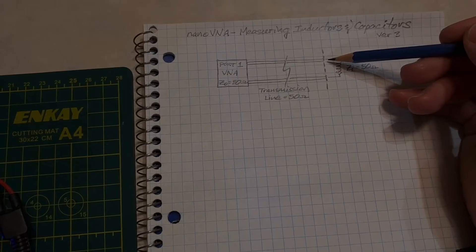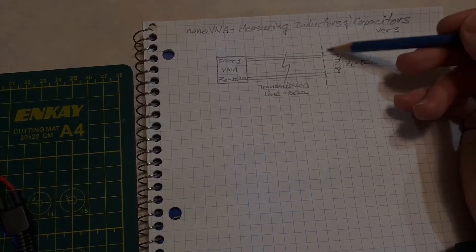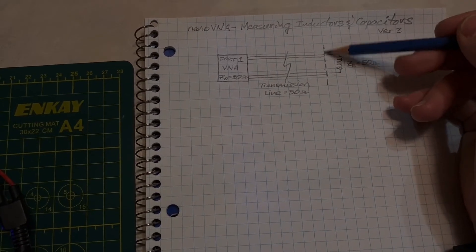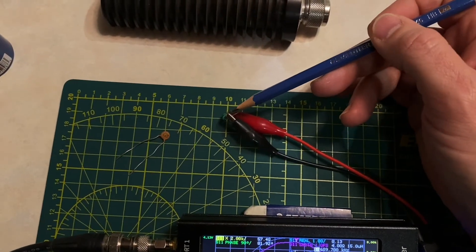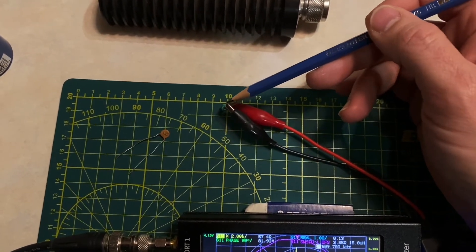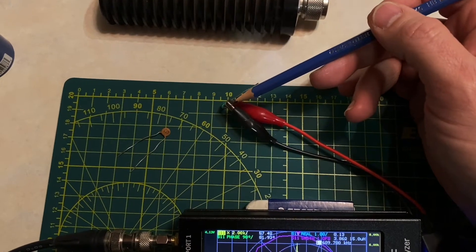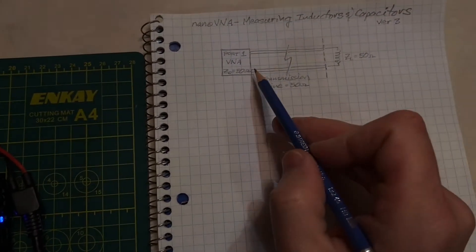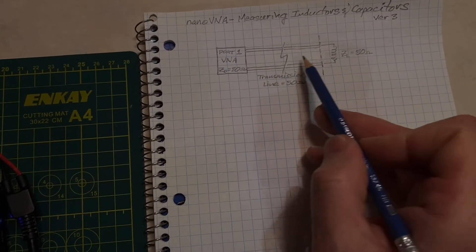This, by the way, is the reference plane where I've calibrated the Nano VNA to examine the device under test with reference to this plane. That calibration plane is right here at the end of these alligator clips. I'll show you how I did that in a second. It's very simple.